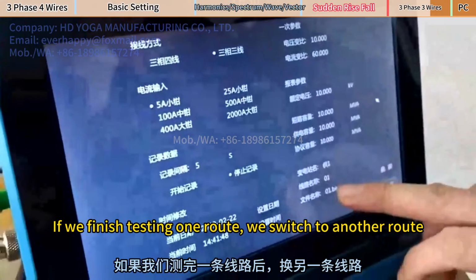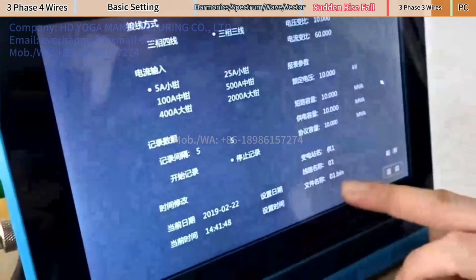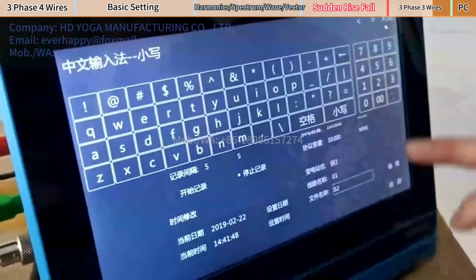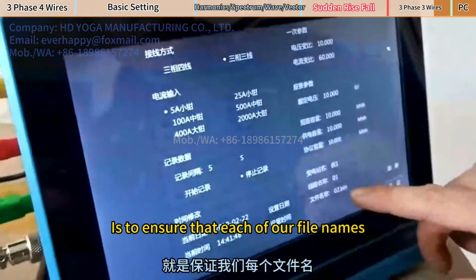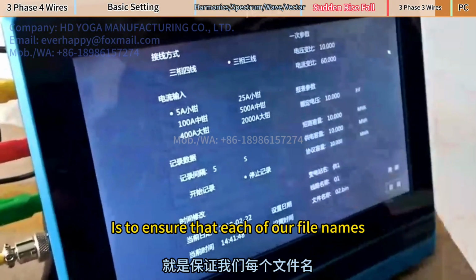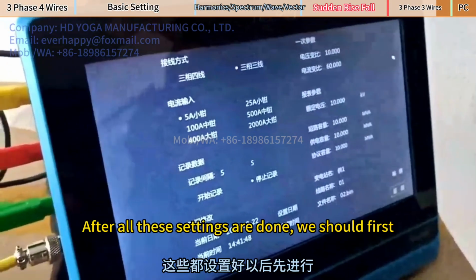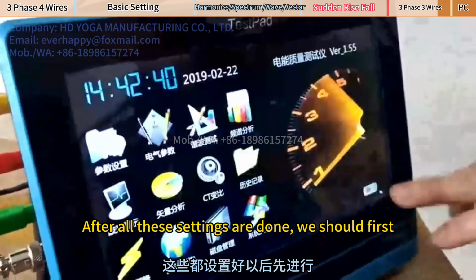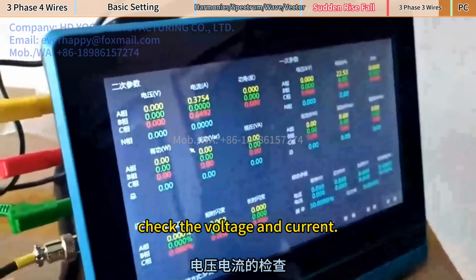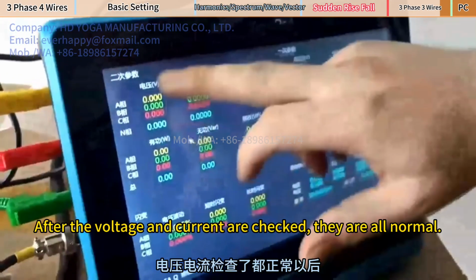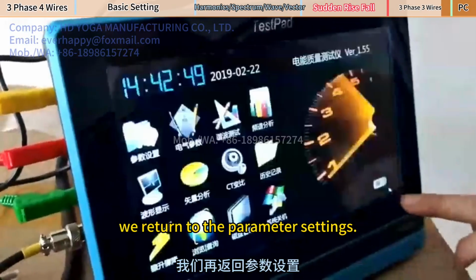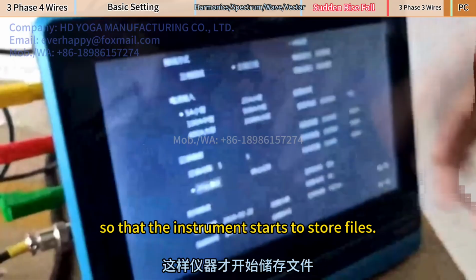If we finish testing one route, we switch to another route. We must change the file name. Is to ensure that each of our file names corresponds to each test point. After all these settings are done, we should first check the voltage and current. After the voltage and current are checked, they are all normal. We return to the parameter settings. Click Start Recording here, so that the instrument starts to store files.